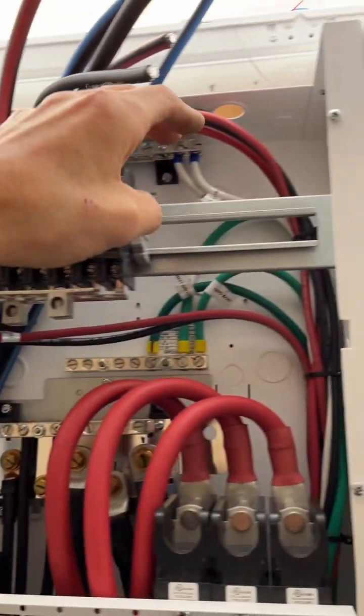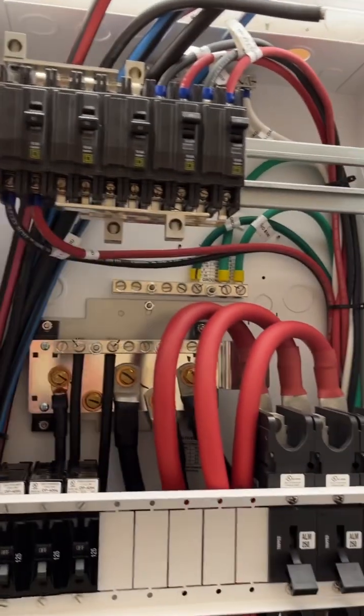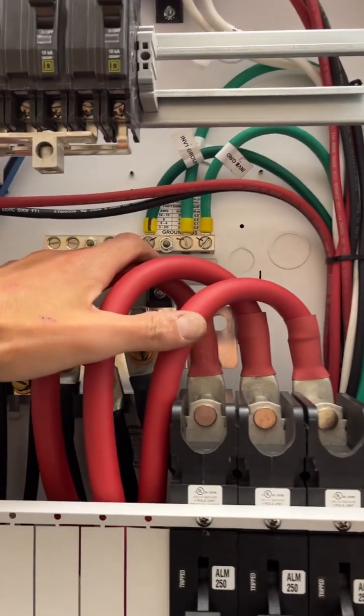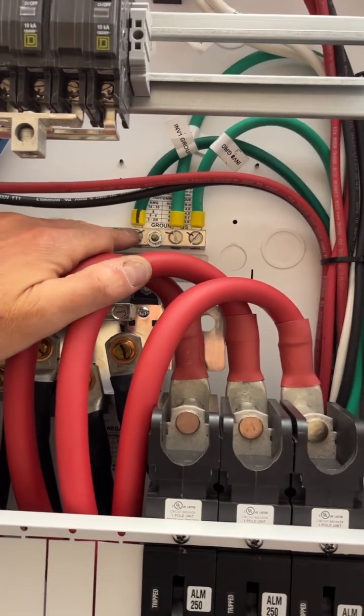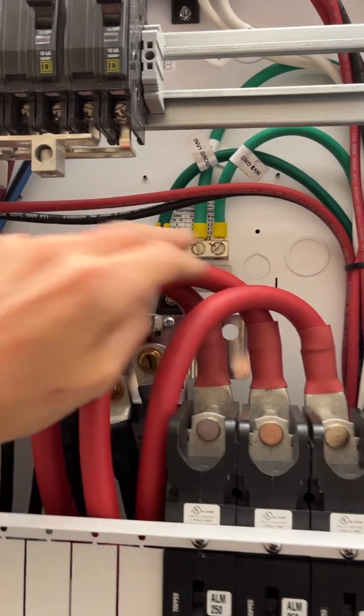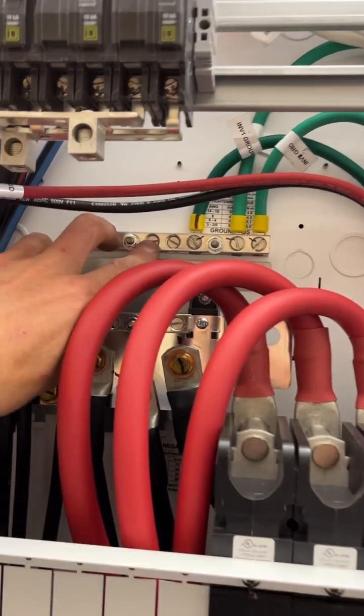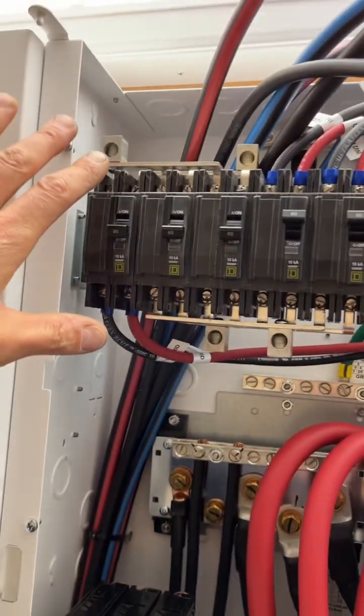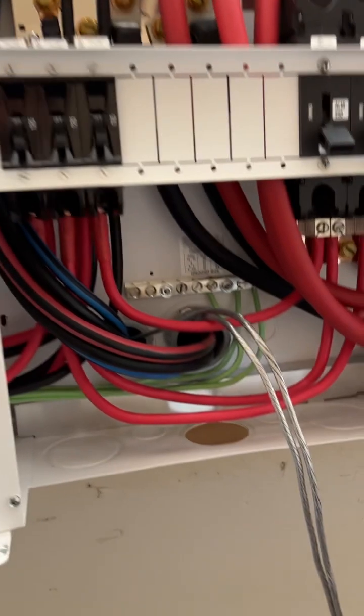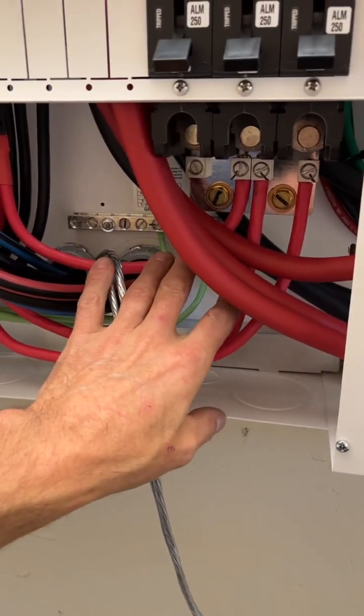Again, no-ox on there. There'll be ring terminals going into the box, ring terminals coming out of the box to connect that up. Everything's been torqued and then marked. When you install something and you torque it, mark it and then go to the next bolt. Don't torque all these and then mark them all because you may miss one unintentionally. Making sure that you do things one at a time. It's been all day, it's been six hours working on the red cables. These things are some stuff.